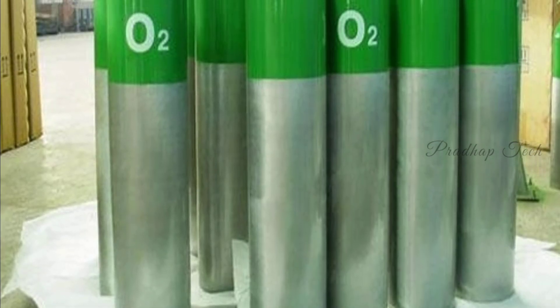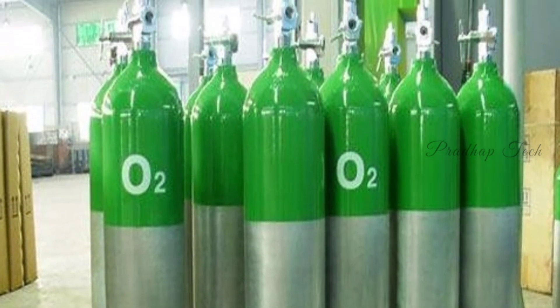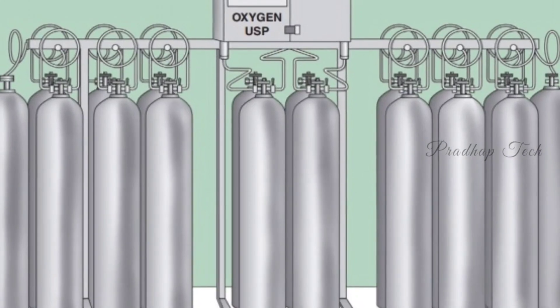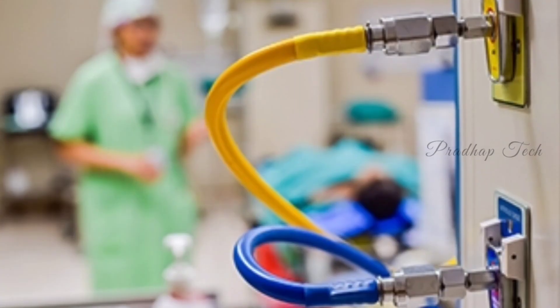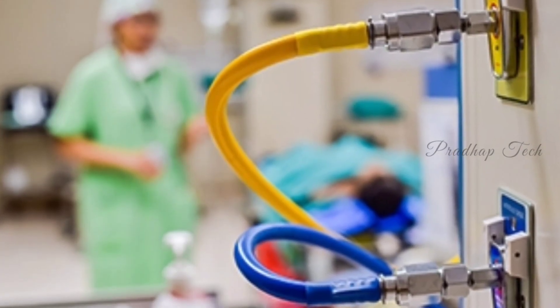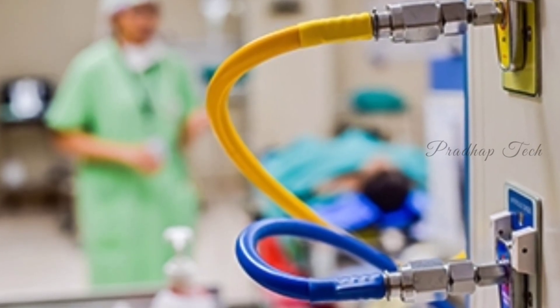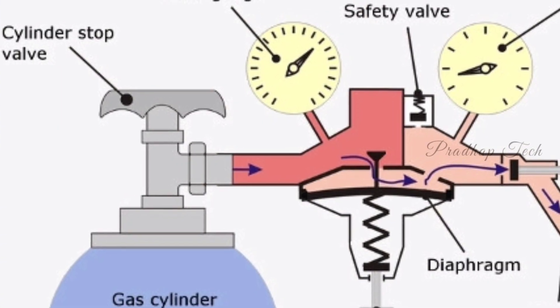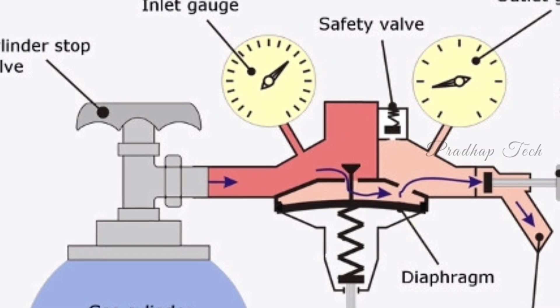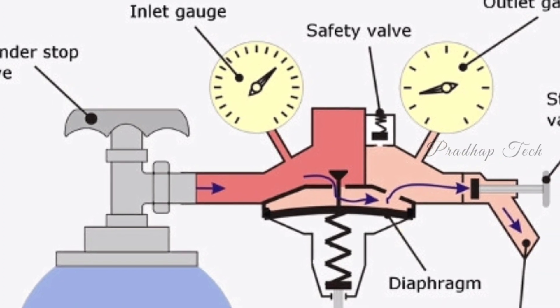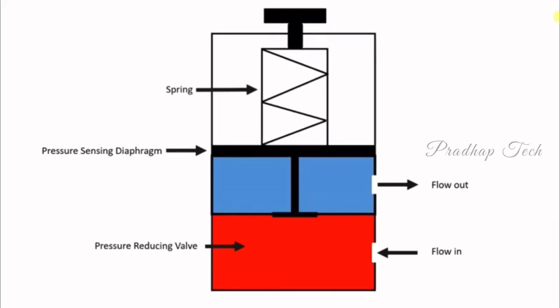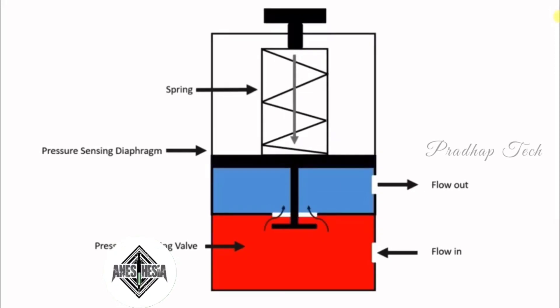Any gas mixture is stored in big tanks or cylinders. Through the pipeline, it is transferred into various departments like the operation theater, ICU, and ward. There will be a yoke assembly and cylinders for opening. Besides, there will be a pressure gauge to measure the pressure. Then coming to the anesthesia machine, there are a pressure-reducing valve and pressure-releasing valve, which reduce the majority of the pressure.